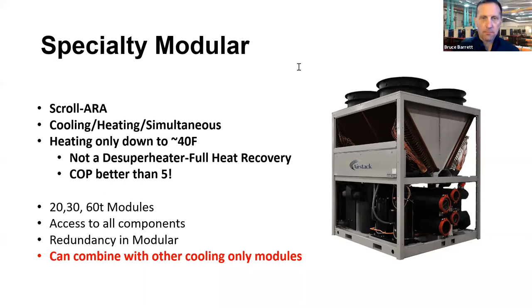Yeah, of course. There'd probably be some balancing to make sure each chiller gets the right amount of flow. Whether they're in parallel with the other chiller, that does present a problem. If your pump set point is 15 PSI to get water through the one chiller, but the next chiller is 20 PSI, there's got to be some balancing that needs to be taken into account. But yeah, absolutely can be done.